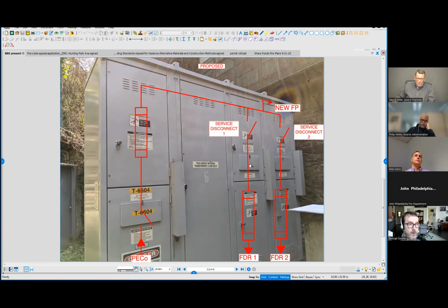When you say three fails, can you go through those? We have fusing, we have switch 1 and switch 2, and we also have switch 3 right here, the main service switch. All of those switches could be opened and we have no power to the building. Well, that's what the signage is intended to address, which switches open and which switches stay closed. I don't see it.